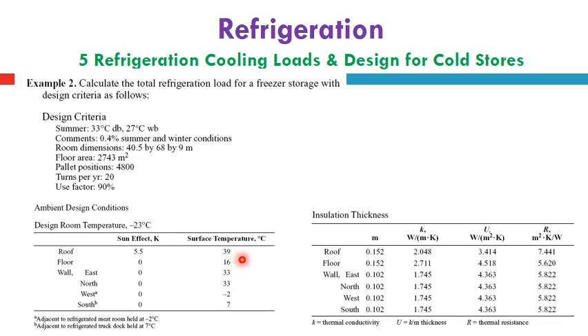The floor is taking 16, and the west has a surface temperature of -2, and the south is 7, due to its adjacent refrigerated meat room being held at -2, and the truck dock being held at 7 from the east side and from the south side. It takes no effect on the east or north side, so it takes the same outside temperature as it is. However, adding the additional temperature.